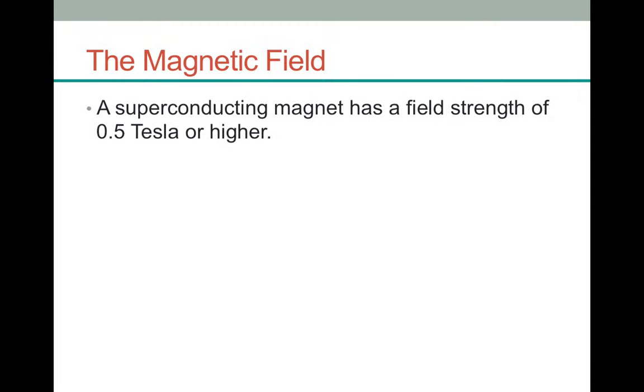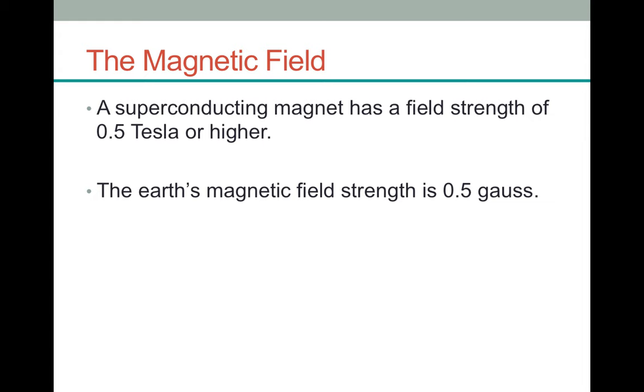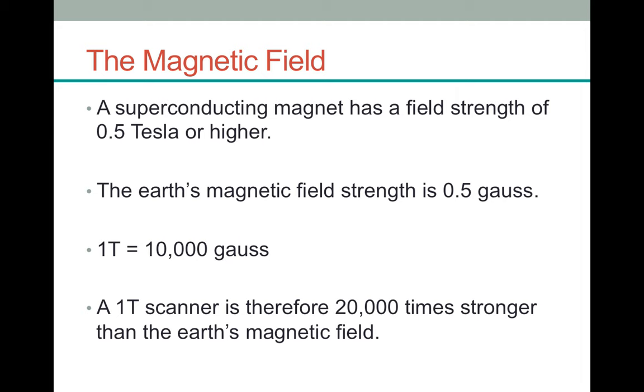A superconducting magnet has a field strength of 0.5 T or higher. At the MRI centre where I work, we have two scanners — one is 1.5 T and the other is 3 T. To put things into perspective, the Earth's magnetic field is 0.5 Gauss, and one Tesla equals 10,000 Gauss. This means a one Tesla scanner is 20,000 times stronger than the Earth's magnetic field. A 3 Tesla scanner is 60,000 times stronger, and in some centres such as Nottingham, where they have a 7 T scanner, that would be 140,000 times stronger than the Earth's magnetic field.